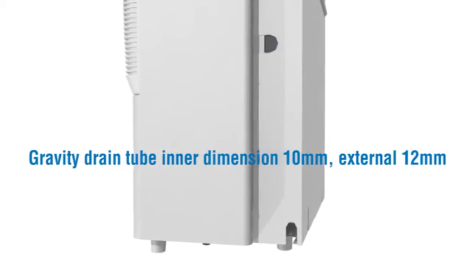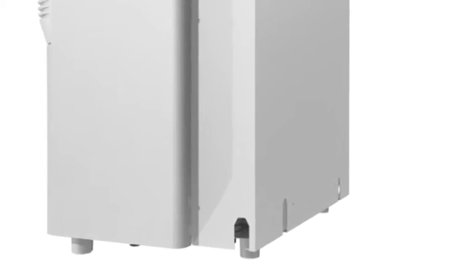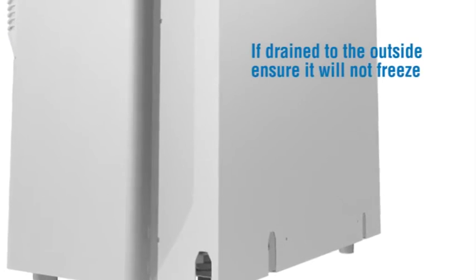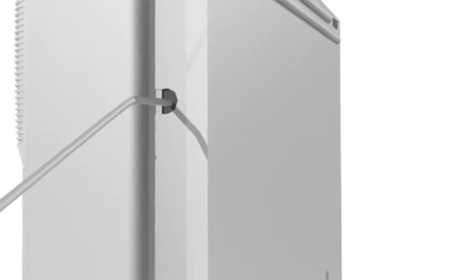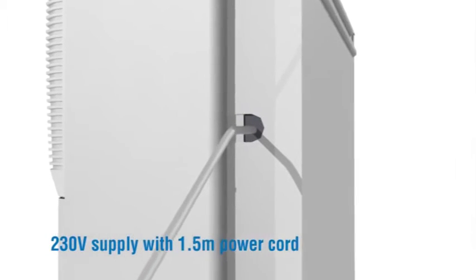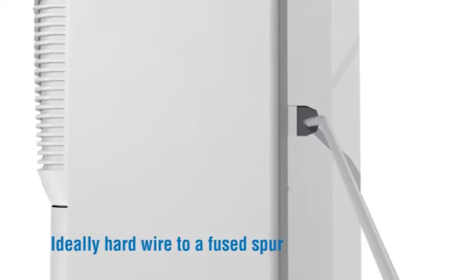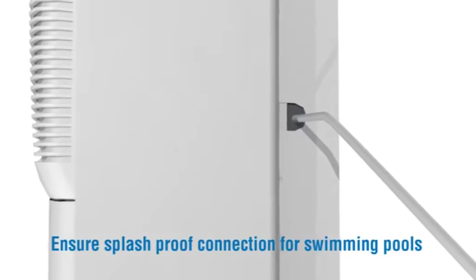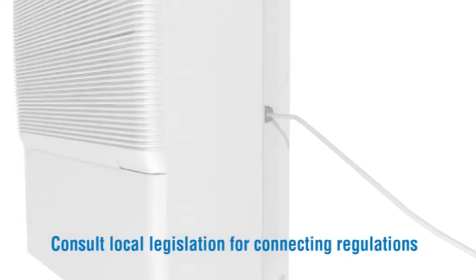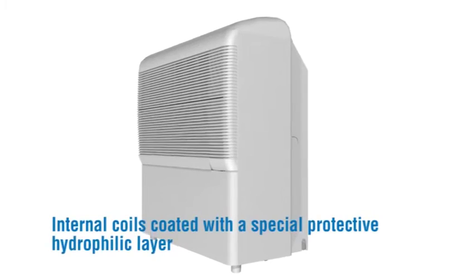Drain tube dimensions: 10 millimetres internal, 12 millimetres external. Ensure the drain tube is free from kinks and cleaned of any mold periodically. If draining to the outside, ensure it will not freeze. 230 volt supply with 1.5 metre power cord — ideally hardwired to a fused spur. Ensure splash-proof connection for swimming pools and consult local legislation for connecting regulations.